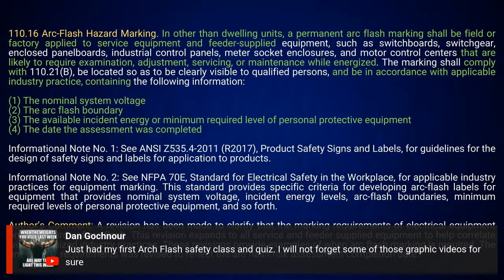It'll have the nominal system voltage, the arc flash boundary, and then it'll say at number 3, the available incident energy or minimum level of PPE. It's going to have at least one of the following listed there, and that's the equipment labeling. Then when you look at how often you need to do it, 130.5 tells you that you need to do that at least once every 5 years.